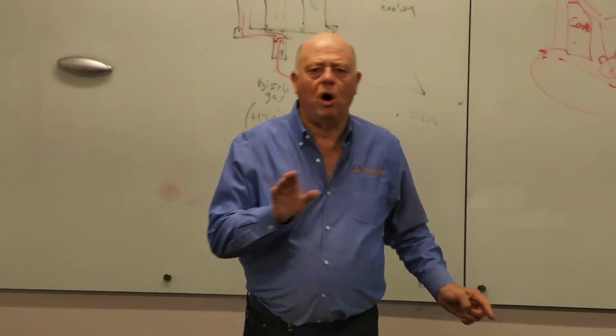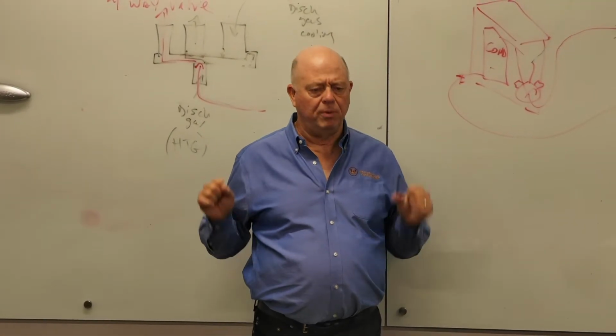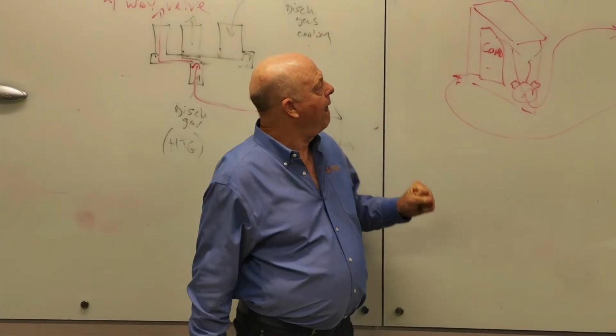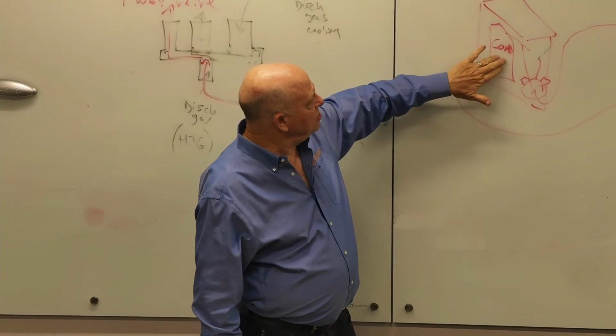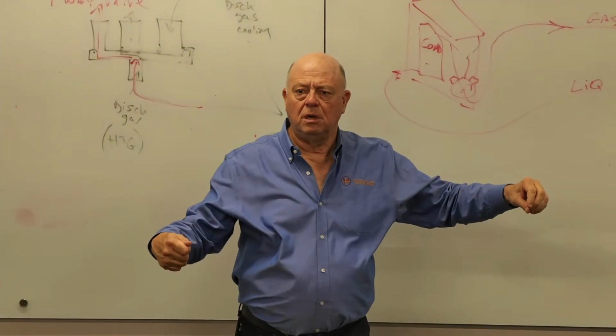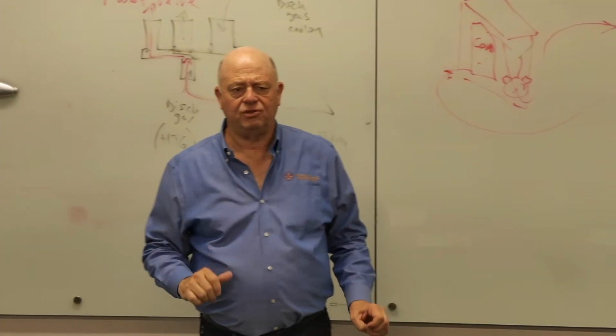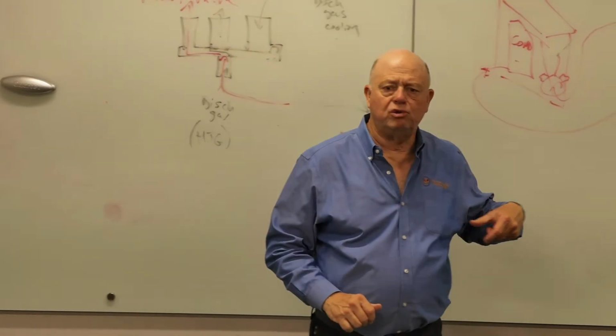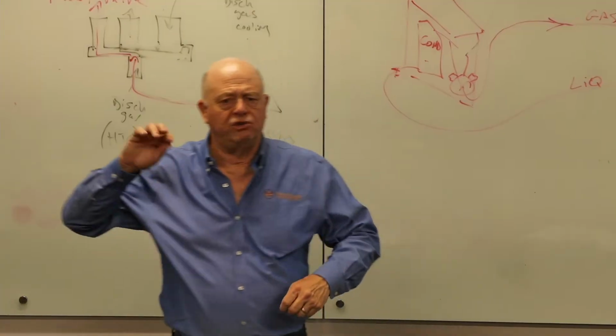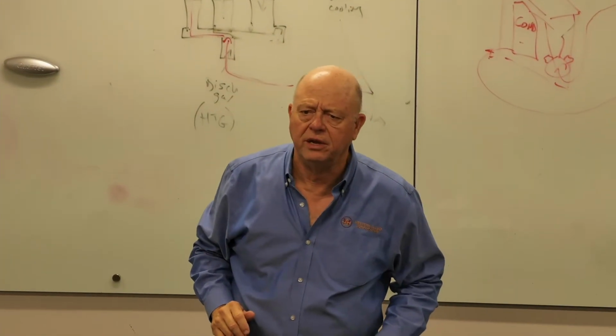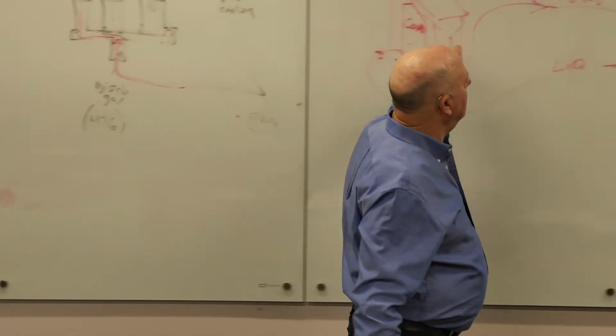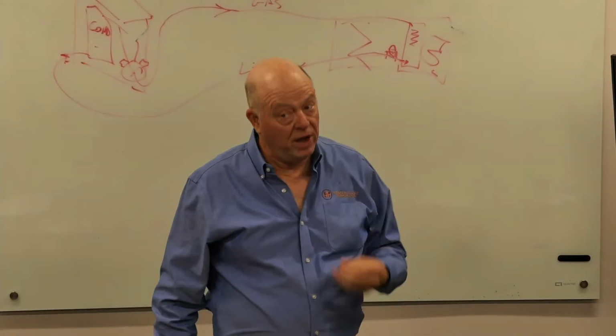There's another nuance, and people get in trouble with this all the time. Think about it. If this is going to work both ways, and you're going to have the right number of passes, and you're going to have the right superheat on the suction side and the right subcooling on the condensing side, that coil and this coil have got to be matched.